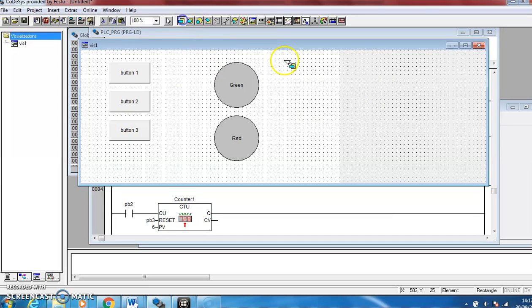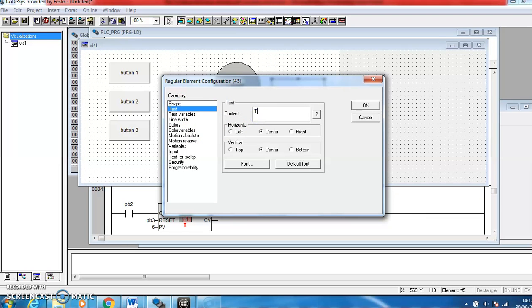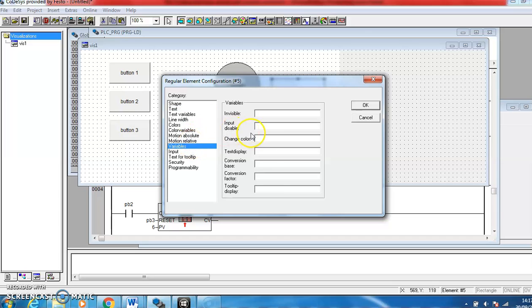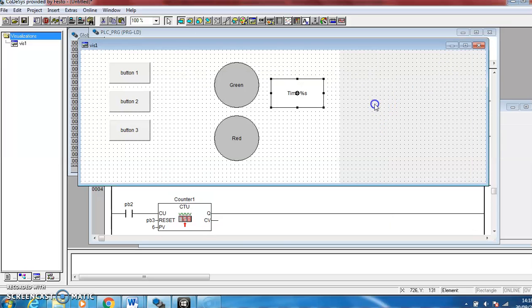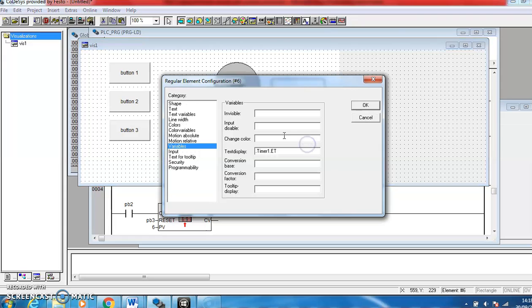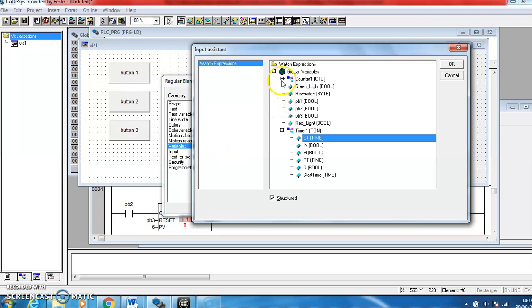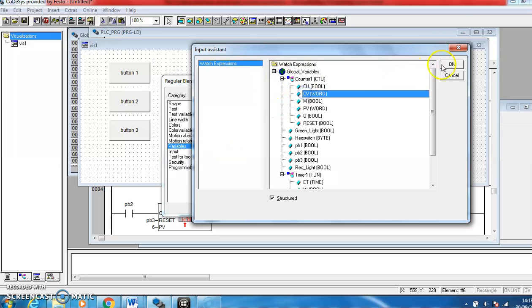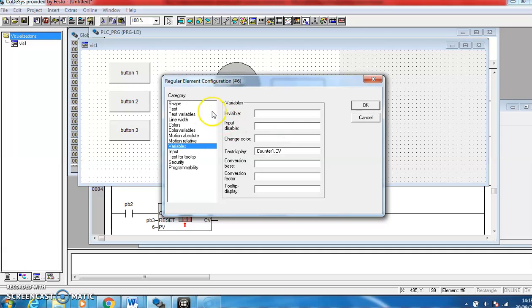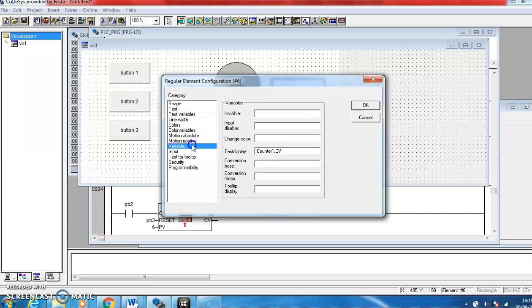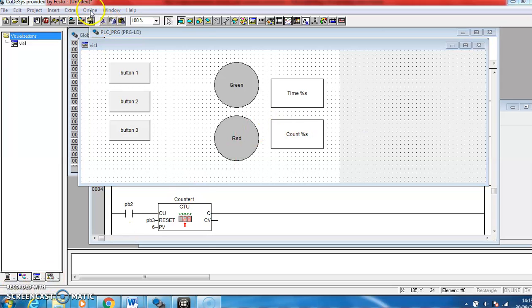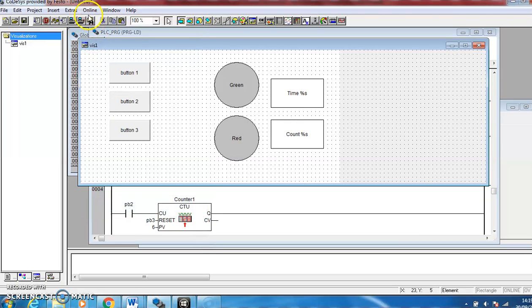And then the other thing I can do is show what the timer is doing. So if I just type in Time, use a little piece of code %s, and then go to variables on text display and connect it to the ET elapsed time of the timer. And do the same for the counter, connect that one to the current value. That should be it. We go to simulation mode, click it, go online, login and online run.